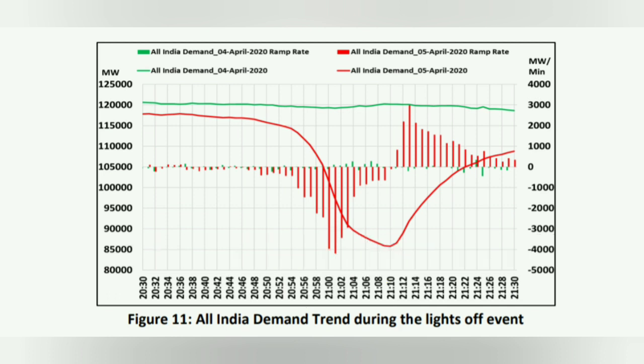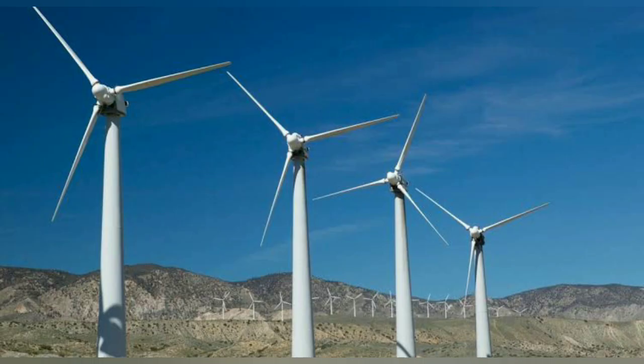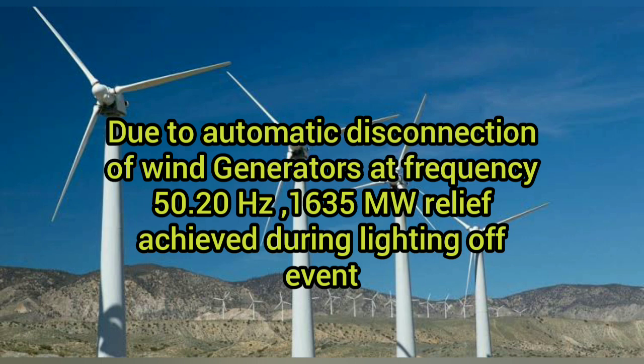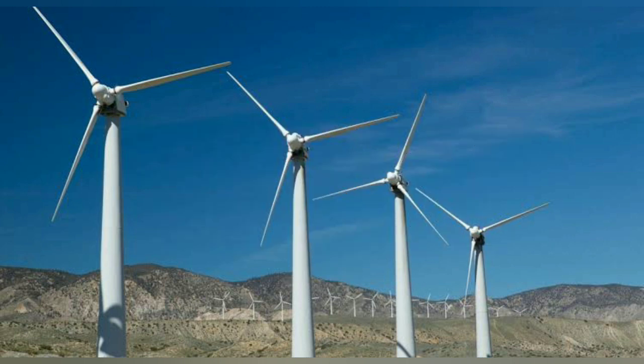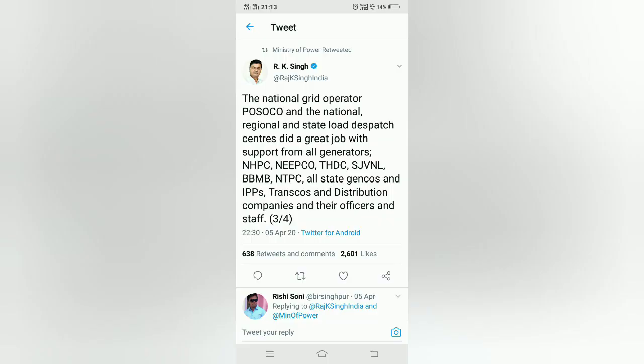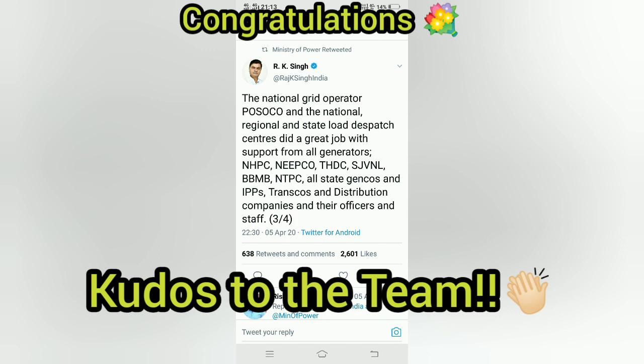Grid frequency touched 50.20 Hz at 9:01 p.m., and with the implementation of over frequency settings for wind generators, that is, automatic disconnection of generators in case of frequency going beyond 50.20 Hz, relief of around 1635 megawatt was received from wind generators between 9:01 p.m. and 9:10 p.m. from automatic and manual tripping of the feeders. Further, no undesirable trippings or untoward incident was observed during the event.